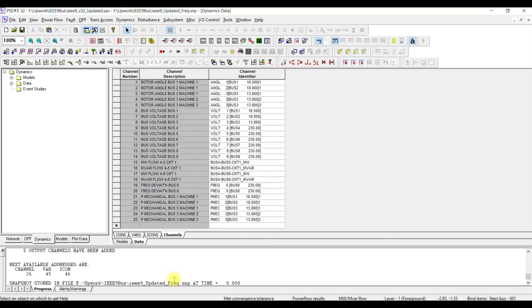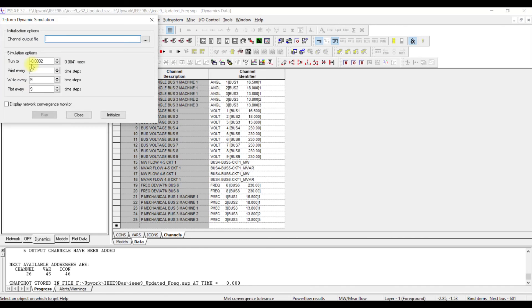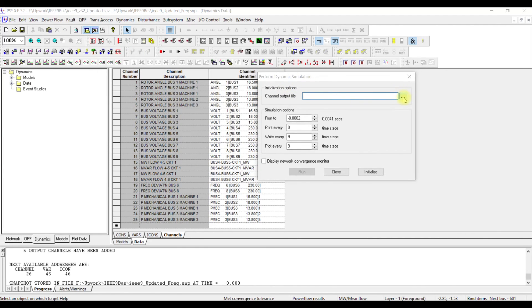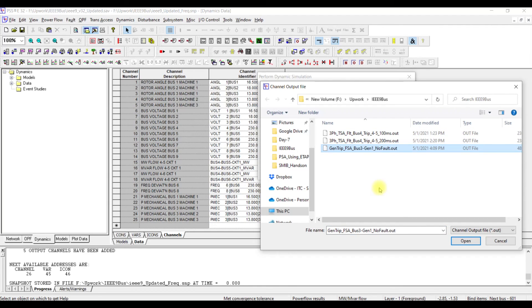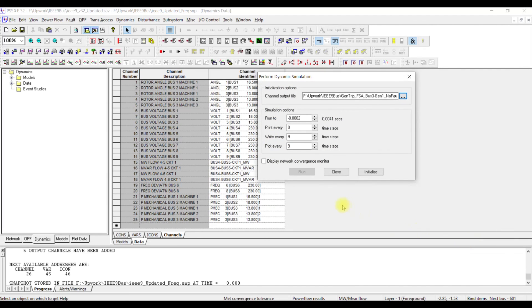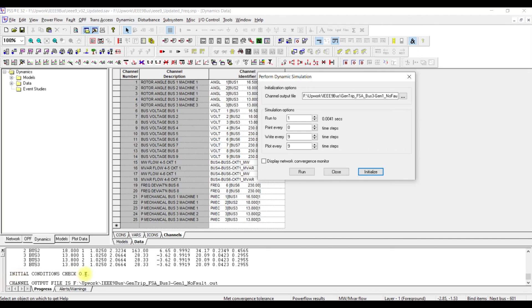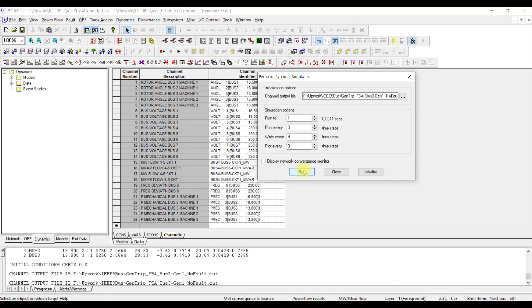To perform the simulation, go to Dynamic Simulation. In the window that opens, select the channel output file and give it a descriptive name — 'Generation Trip' — for frequency stability analysis, noting that we are tripping generator 1 at bus 3 without any fault. Press Open. Next, initialize the case by selecting Initialize — the initial condition check passes and everything is okay. Run the case for one second without any disturbance by pressing Run.